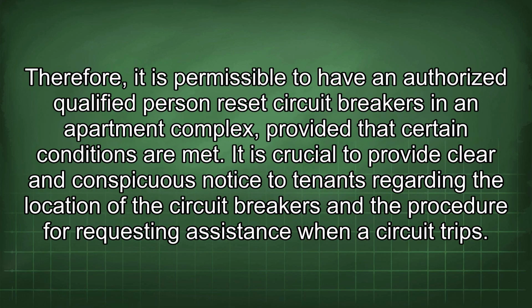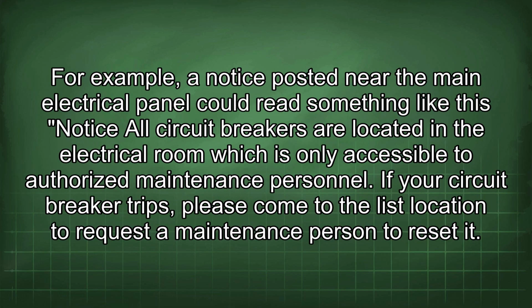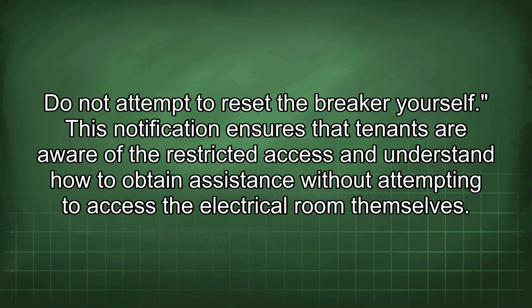Therefore, it is permissible to have an authorized qualified person reset circuit breakers in an apartment complex, provided that certain conditions are met. It is crucial to provide clear and conspicuous notice to tenants regarding the location of the circuit breakers and the procedure for requesting assistance when a circuit trips. For example, a notice posted near the main electrical panel could read something like this: "Notice: all circuit breakers are located in the electrical room, which is only accessible to authorized maintenance personnel. If your circuit breaker trips, please come to the listed location to request a maintenance person to reset it. Do not attempt to reset the breaker yourself."